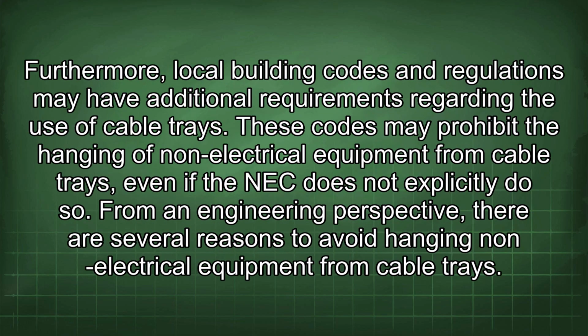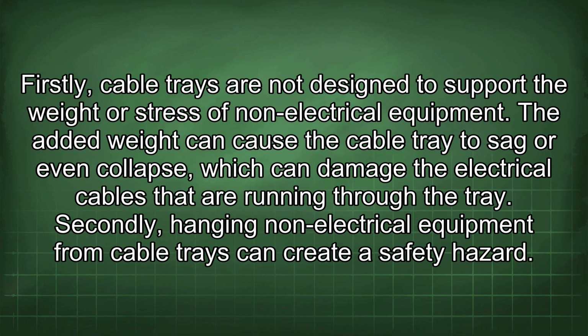Furthermore, local building codes and regulations may have additional requirements regarding the use of cable trays. These codes may prohibit the hanging of non-electrical equipment from cable trays, even if the NEC does not explicitly do so. From an engineering perspective, there are several reasons to avoid hanging non-electrical equipment from cable trays. Firstly, cable trays are not designed to support the weight or stress of non-electrical equipment. The added weight can cause the cable tray to sag or even collapse, which can damage the electrical cables that are running through the tray.